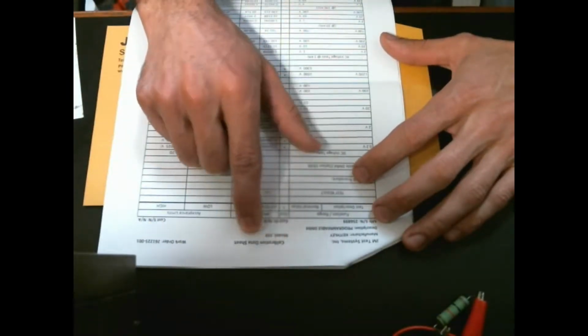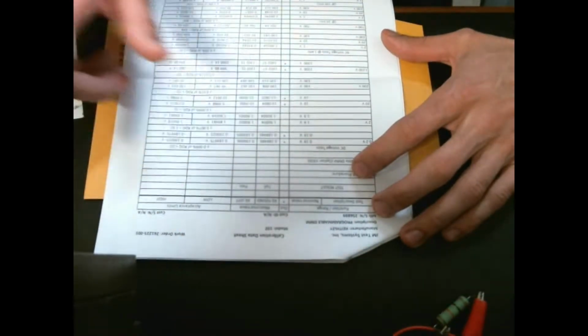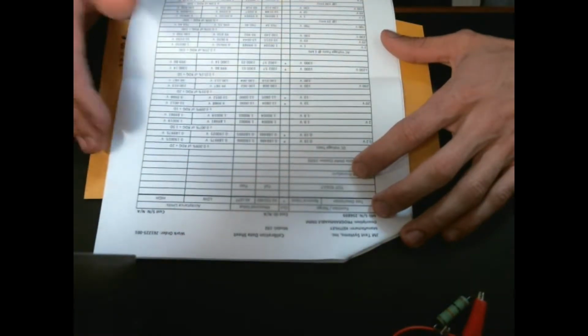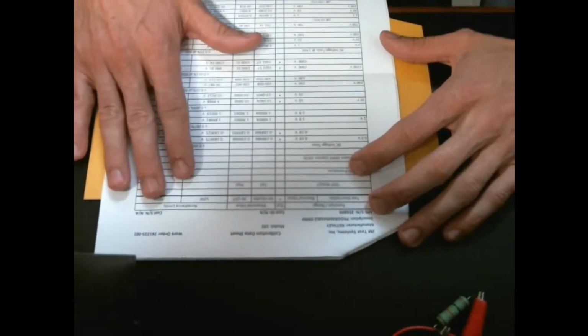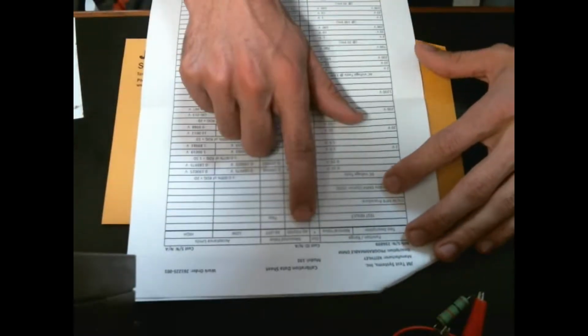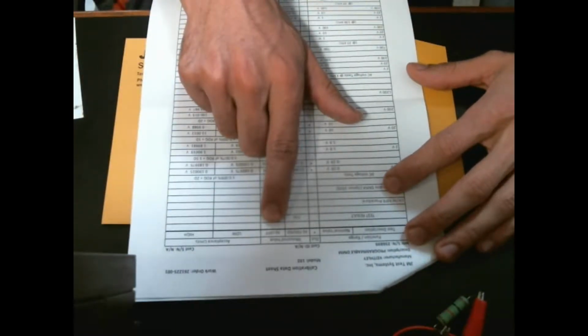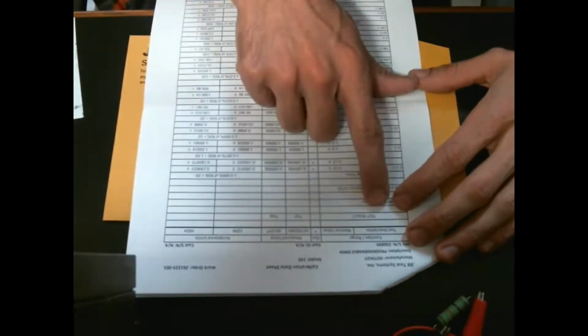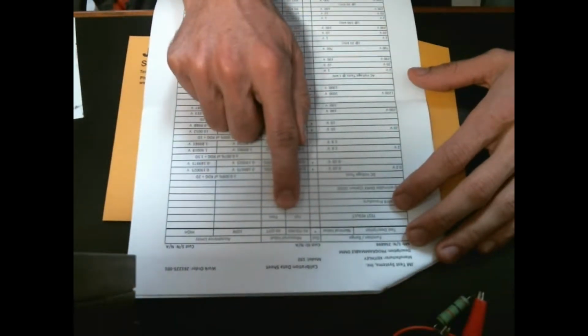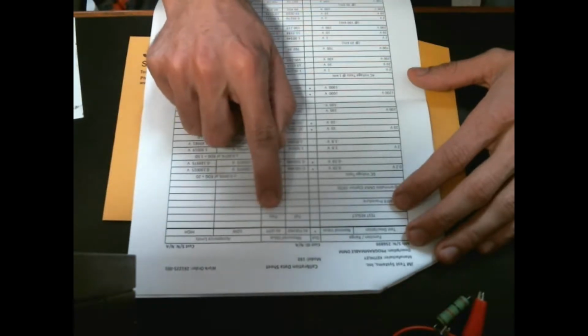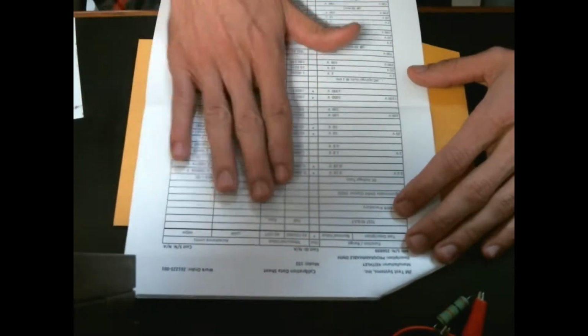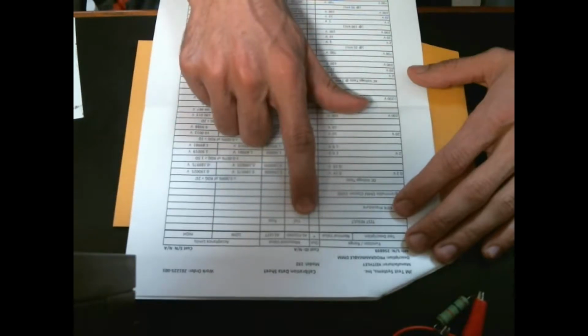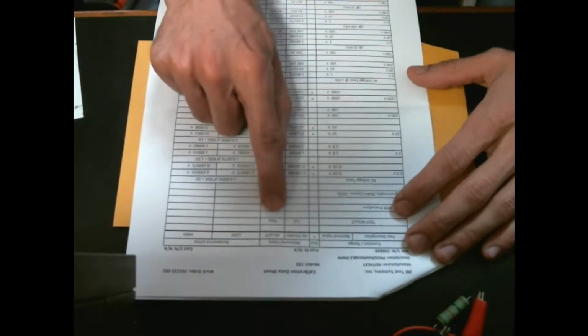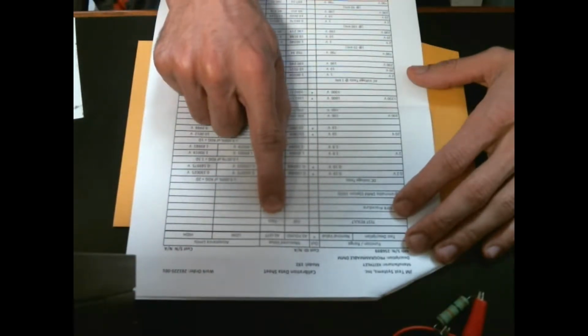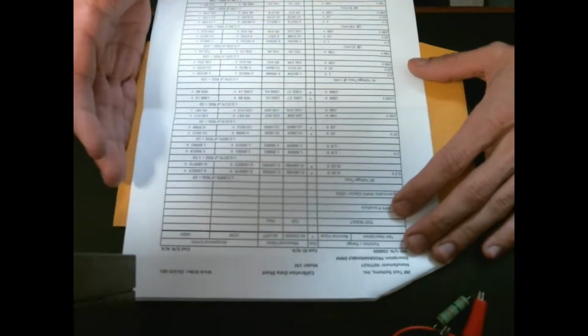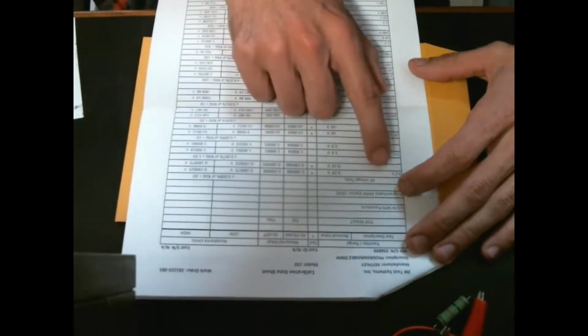At the top you can see they call this the calibration data sheet, which I call the table of offsets. This is probably the more proper term for it. And here you can see the as found, as left, and test result. You can see that my meter failed, but as left, it passed. So it's very important that this shows that at first it did fail, but they were able to adjust it in the spec. So that tells us that the meter wasn't broken, it had just drifted out.